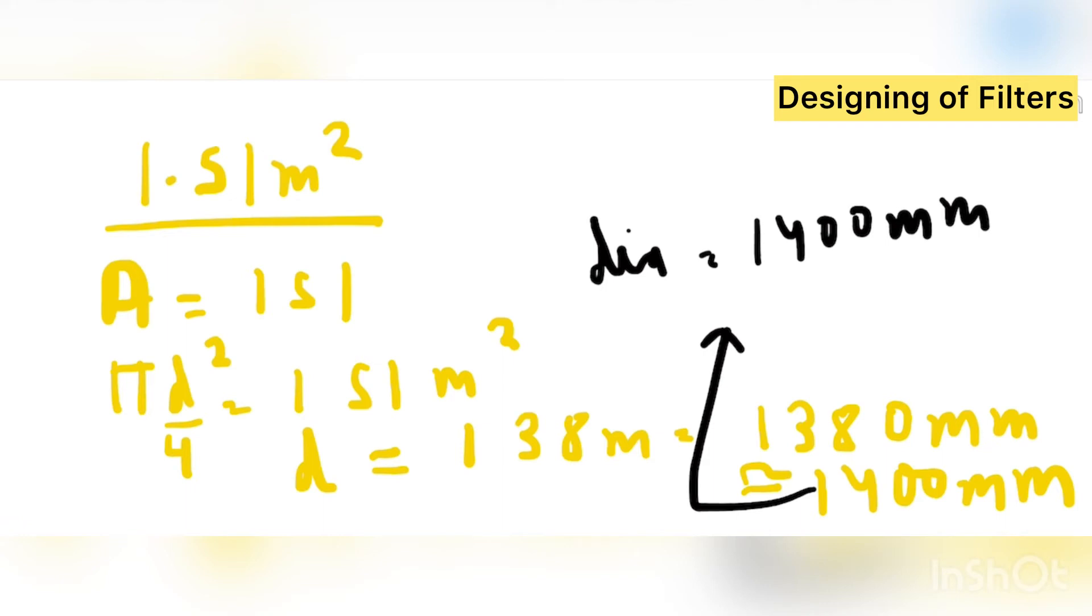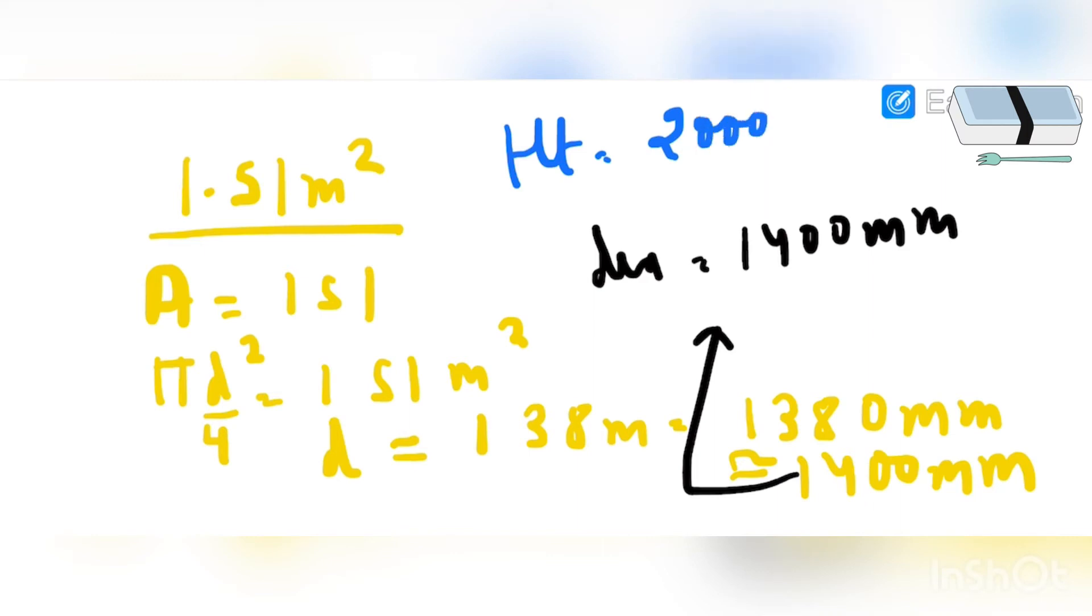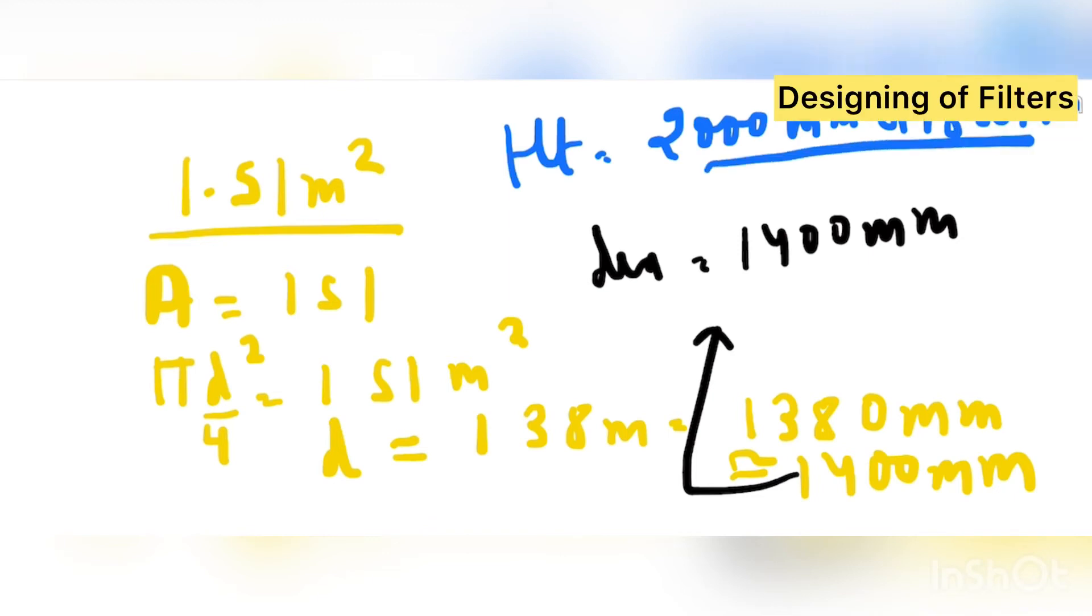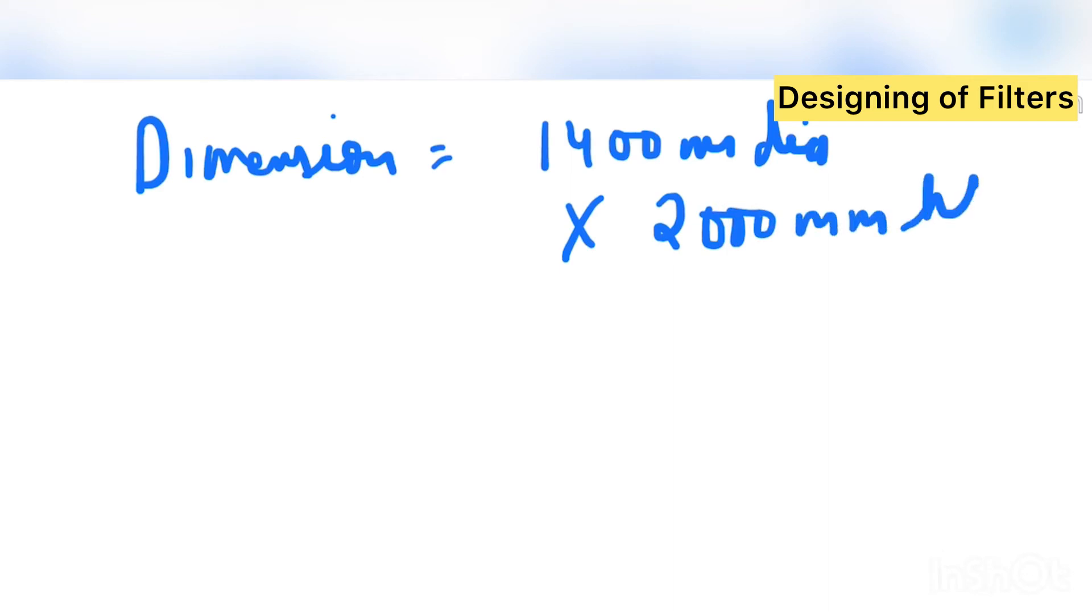So what is the height. Now height is, how we come to the height. Generally height is taken as a standard. In filtration system we consider height is 2000 mm or 1800 mm. So overall the dimension which I am getting of activated carbon filter is 1400 mm is the diameter into 2000 mm as height. So we will see one more example.